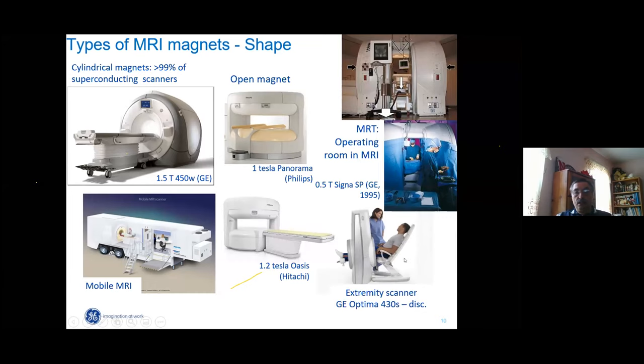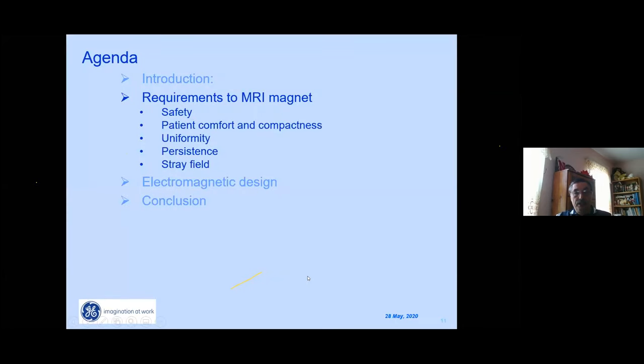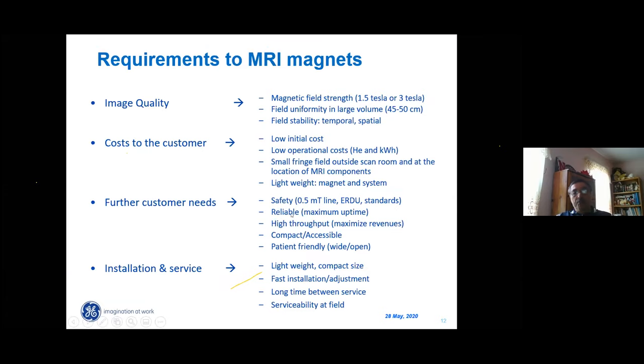And another, it's a so-called specialty scanner for musculoskeletal, for foot imaging. Also relatively small market. It appears that cost of whole body cylindrical scanner is about similar as compared to cost of specialty system. So MRI is a cost-driven industry. Okay, let's talk about requirements. I put here some of the requirements, and what we see, it's commercial magnet is always a compromise, multiple conflicting requirements. On one hand, customers want high field, high strength, high uniformity, but they don't want to pay higher price. And as a result, we need to find what is the best compromise, what is exactly necessary to customers.